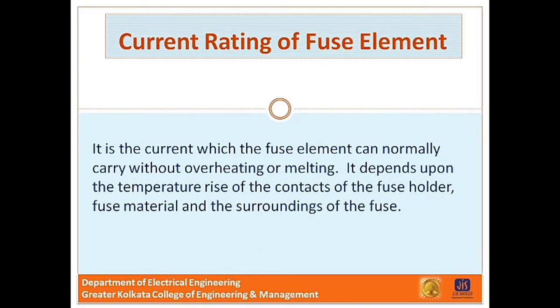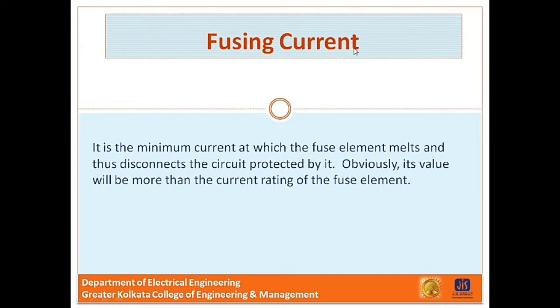Next I will describe some important terms related to fuse. The first is the current rating of a fuse element: it is the current which the fuse can normally carry without overheating or melting. It depends upon the temperature rise of the contacts of the fuse holder, fuse material, and the surroundings of the fuse. This is the normal operating current of the fuse element. Next, fusing current: it is the minimum current at which the fuse element melts and thus disconnects the circuit protected by it. Obviously its value will be more than the current rating of the fuse element.